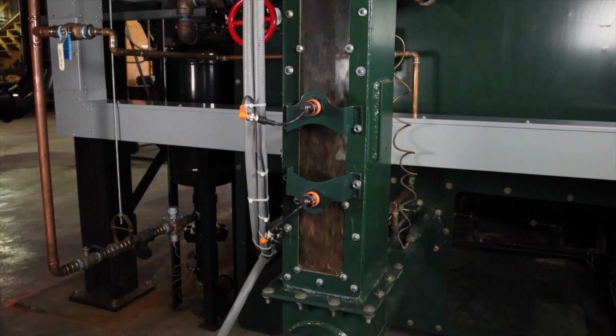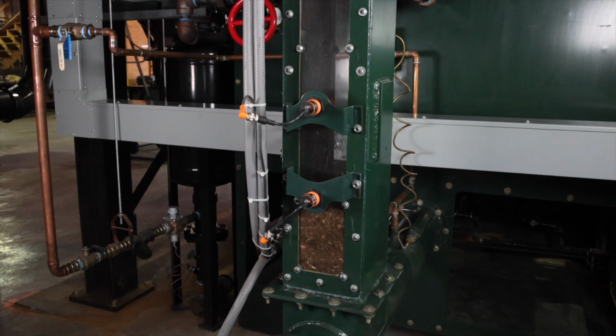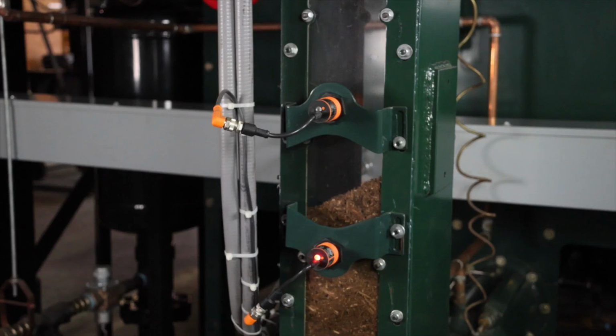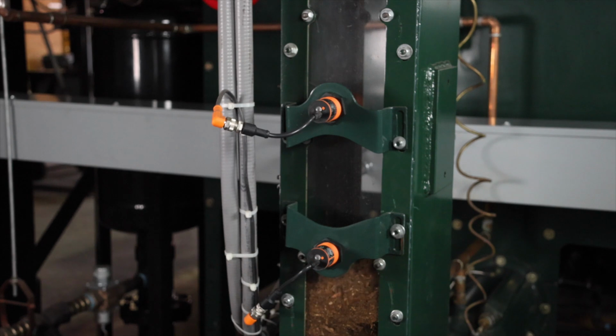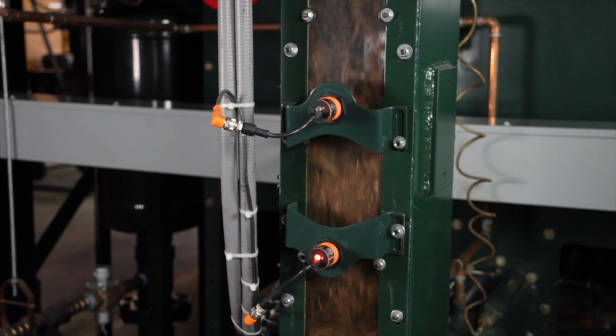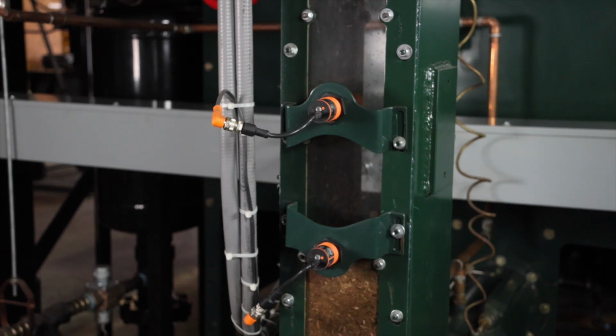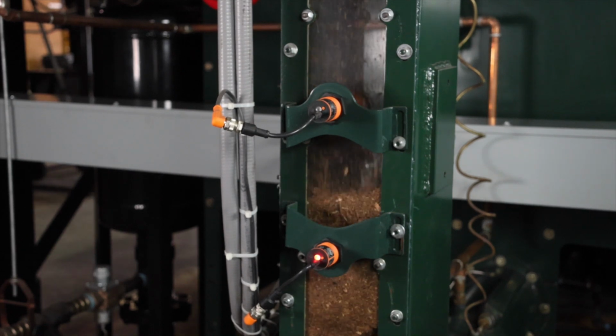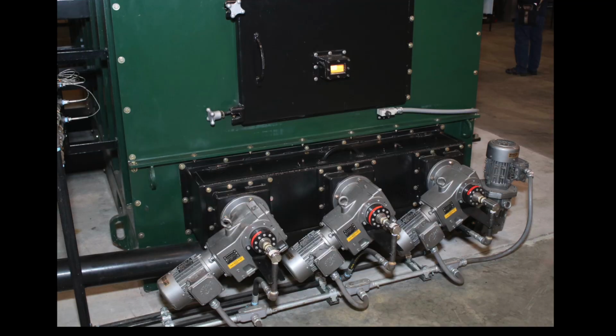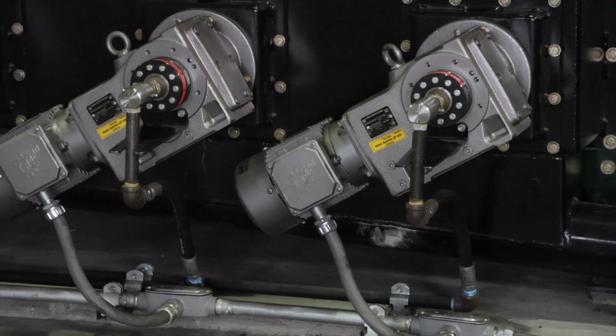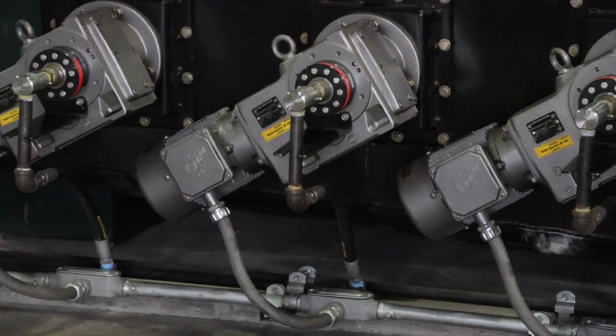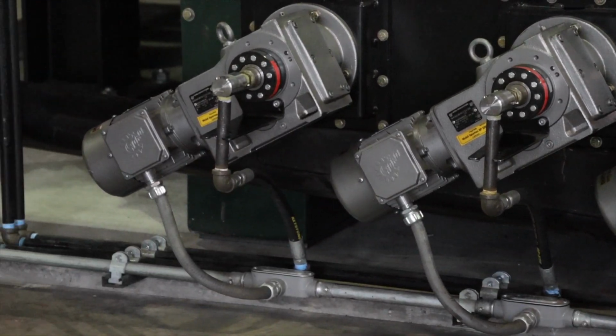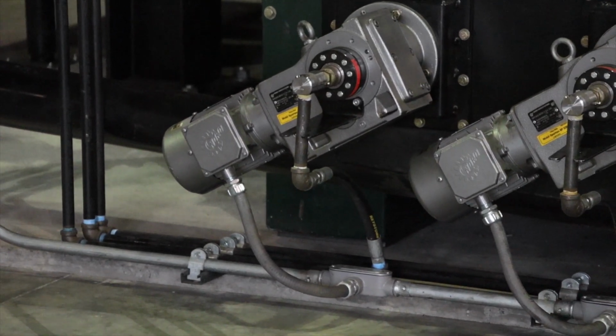Once inside the firebox, the fuel forms a pile and the combustion process begins. The fuel feed rate automatically adjusts by way of a variable frequency drive, which maintains an output matching the load demand. In the firebox are a series of parallel stainless steel augers. These augers evenly distribute fuel and combustion air. They also move the fuel through the firebox until it is in the form of ash, and then remove the ash from the primary combustion chamber.